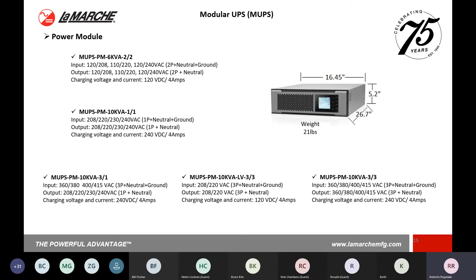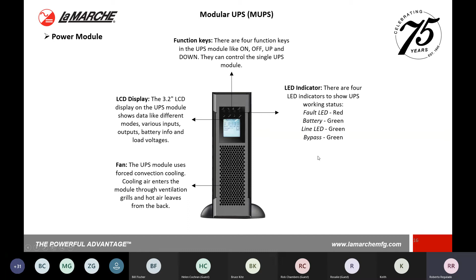Okay, so just a breakdown on the actual power module itself. Obviously these are high frequency. You do have a fan. It's fan assisted, so there is also some type of indication of your fan failing. You do have your LCD display, which is also rotatable. Physically, it doesn't pop out like the compact UPS, but there is a button to rotate it, depending on how your configuration style is. And you do have a few functional buttons on the front of the display to navigate the menu. Probably an easier way to navigate is through the SNMP style communication that comes standard with the MUPS. You do have some of your standard LED indicators for fault and on battery. Your line is there, and your bypass is available as well.